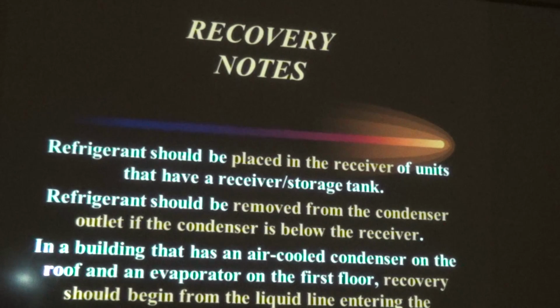Refrigerant should be placed in the receiver of units that have a receiver storage tank. These two are test questions right here. This has to do with gravity when they ask you this. Refrigerant should be removed from the condenser outlet if the condenser is below the receiver. Next one. In a building that has an air-cooled condenser on the roof and an evaporator on the first floor, recovery should begin from the liquid line entering the evaporator. So it's going to be whichever one's the lower one that you're going to see.